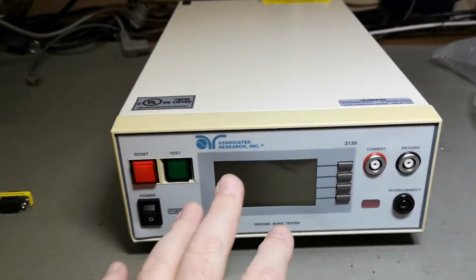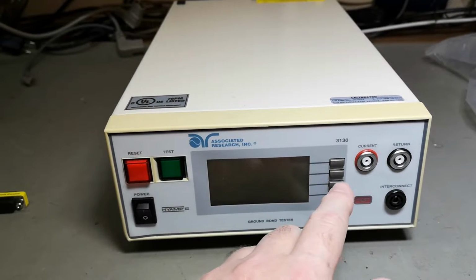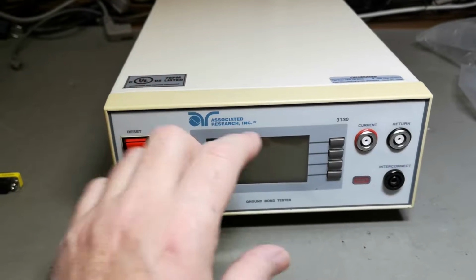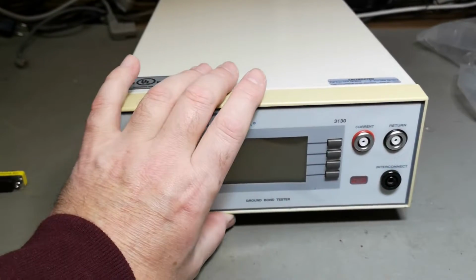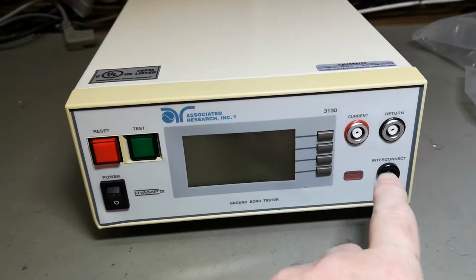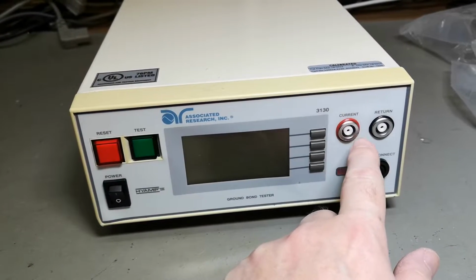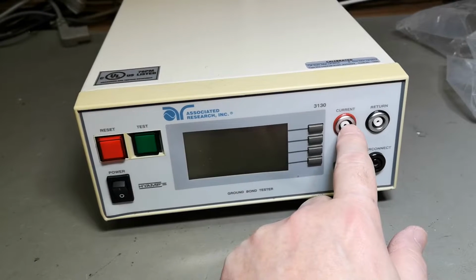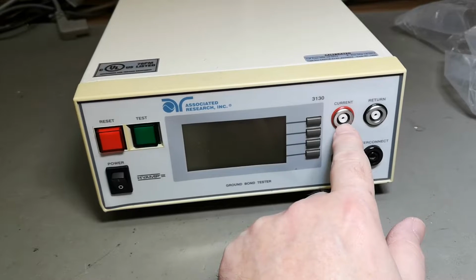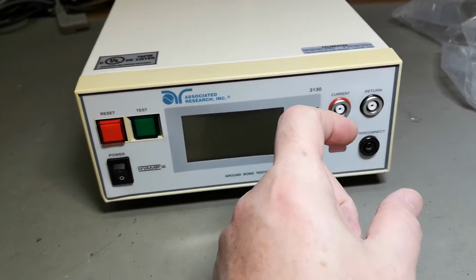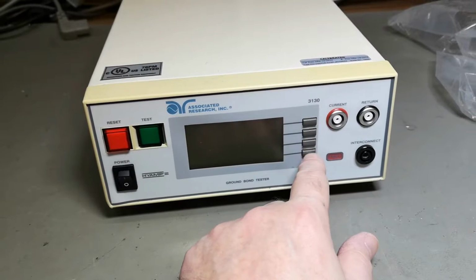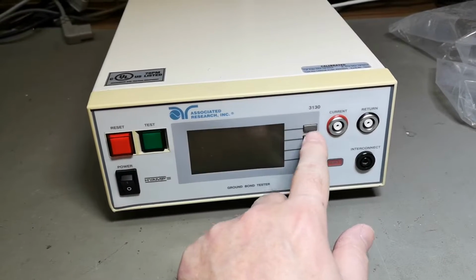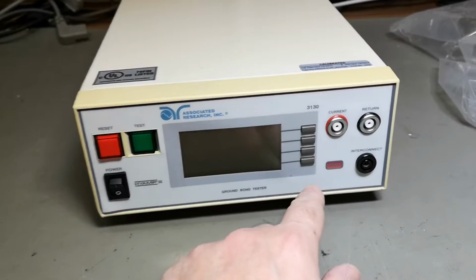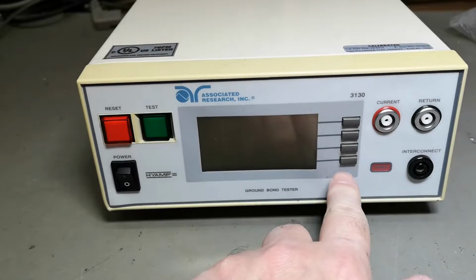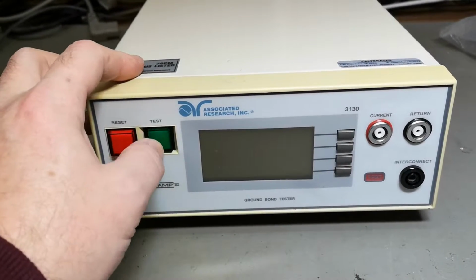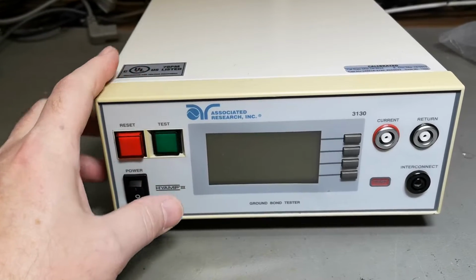As far as I understand, this is a low voltage but very high current test system for testing ground connections, especially earth ground connections in your products. It's able to supply 6 to 8 volts of AC, but it will be able to deliver 40 amps and then measure the voltage drop. This way it can measure resistance in milliohms at very high accuracy and also prove the ground connection is good for all that current. This is required for a lot of high power equipment as a good indicator for safety.